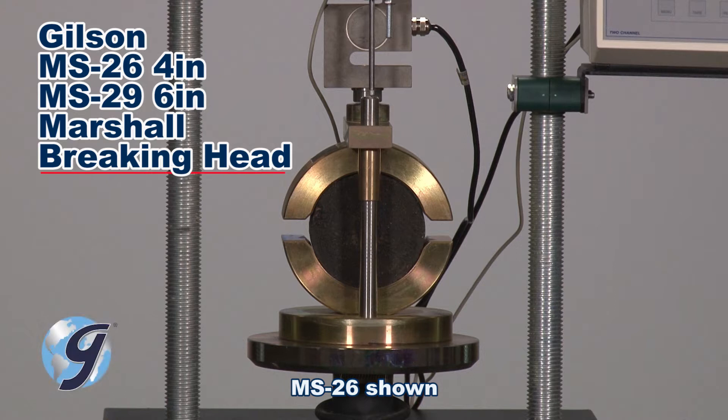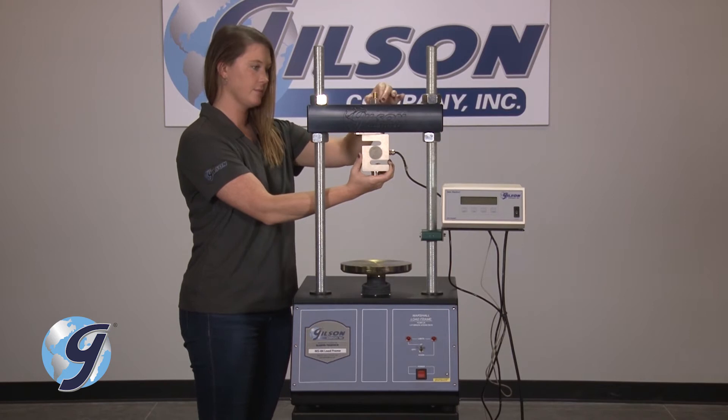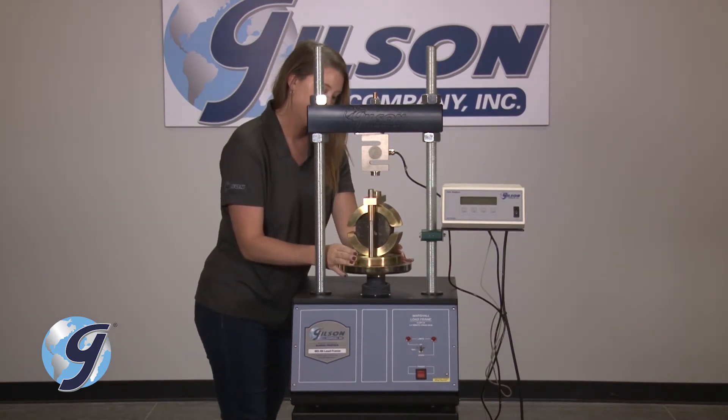The Gilson 4-inch Marshall Breaking Head aids in measuring the load and the flow rate of hot-mixed asphalt specimens. With the indicator bracket already attached to the upper portion of the load cell, attach the load cell to the crosshead. The braking head fixture with asphalt specimen is centered on the platen of the load frame.